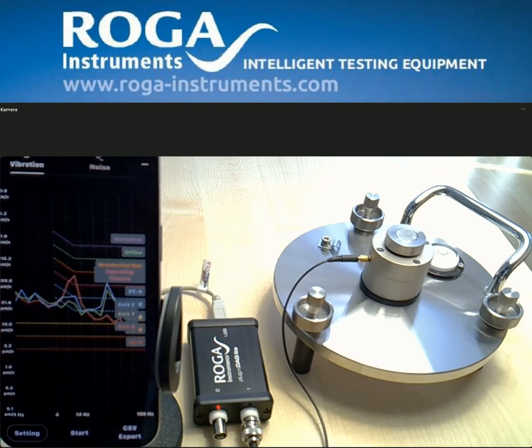So now it's already finished. And now we can see here that the third-octave levels are somewhat raised, and in this case it's not recommendable to install special devices into this building. So this is only one app for vibration criteria measurements, but there are many other apps in the Apple Store.